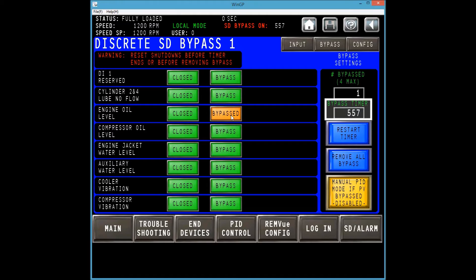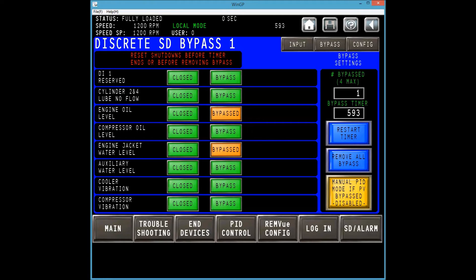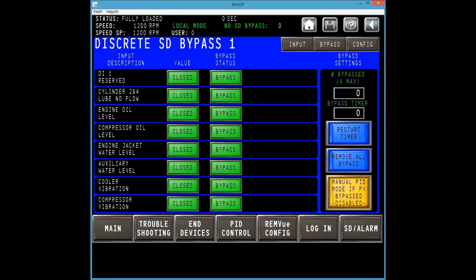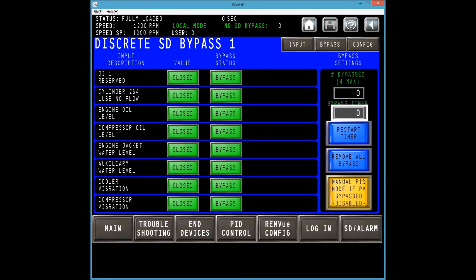If more time is required, the user must press the restart timer to reset the timer to 10 minutes. Note that selecting or deselecting additional bypass states will not restart the timer automatically. When we no longer need to bypass, we can remove this state by pressing the orange button. You will again notice three changes: the orange bypass button will change back to green, the bypass counter will decrease by one, and the bypass timer will either remain running if another channel is still in a bypass state or turn off if no bypass channels remain.